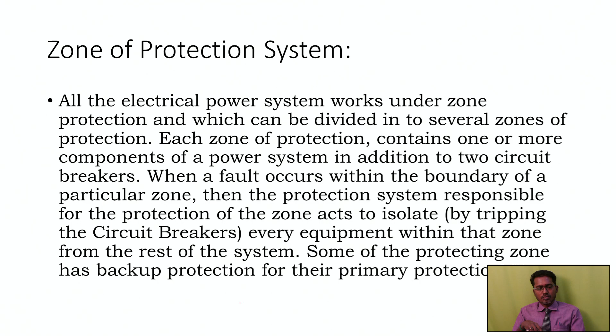Here we have split it zone-wise. In zone 1, the generator and bus bar 1 are considered as zone 1, and again we go for zone 3. The transmission sending end and receiving end are considered as zone 3, and zone 5 is the secondary distribution, with starting end and ending end considered as zone 5. But refer to zones 2 and 4: they combine both the generator part and the transmission part. So we are making overlapping of the protection zones.